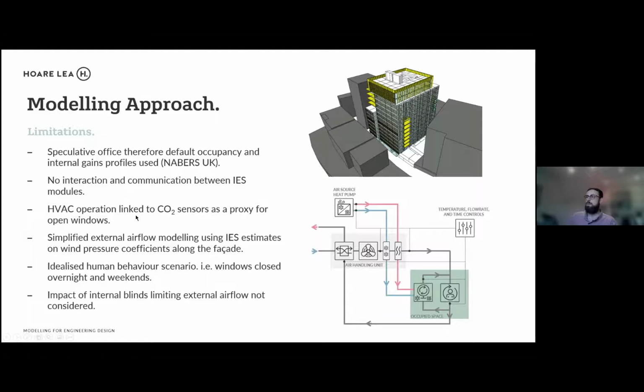For the manually operable windows and just the single-sided windows, there was no intention for an interlink between the ventilation system and the window opening. So there was no sensor on the window to say, if window's open, turn ventilation off. There was no allowance for that.